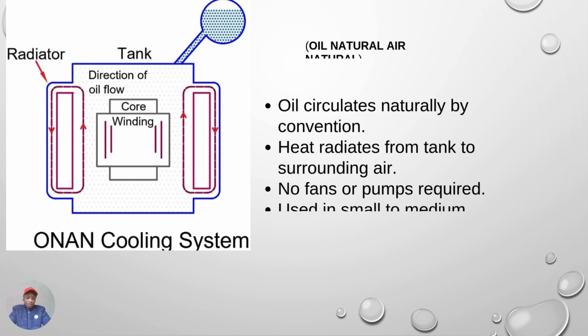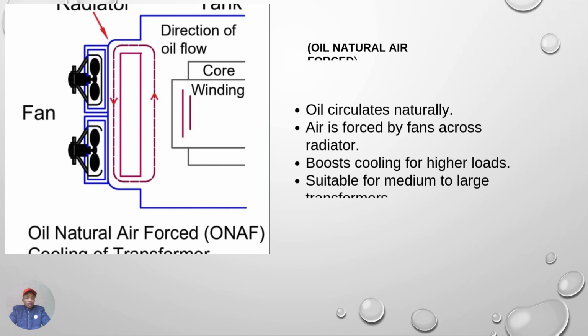Next is the ONAF system. The main difference between ONAN and ONAF is that in ONAF, air is forced. We have fans to blow air across the radiators, but the oil still circulates naturally. Using fans boosts cooling for higher loads, making it suitable for medium to large transformers.